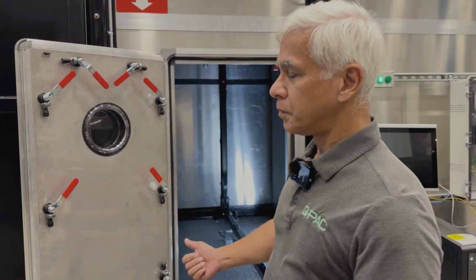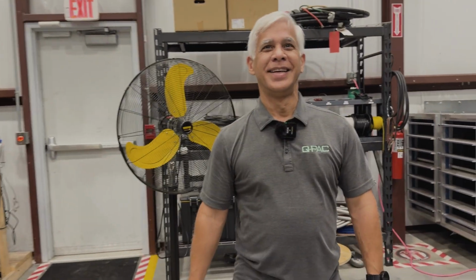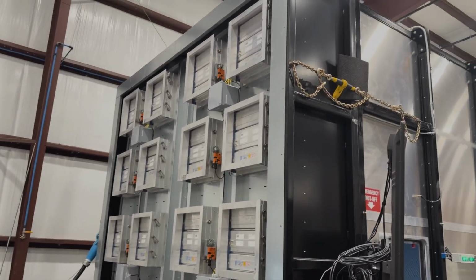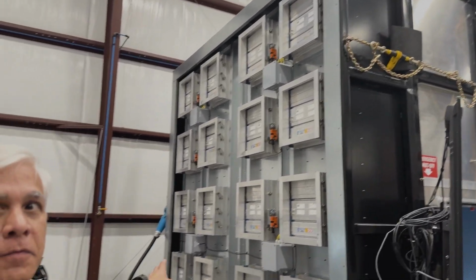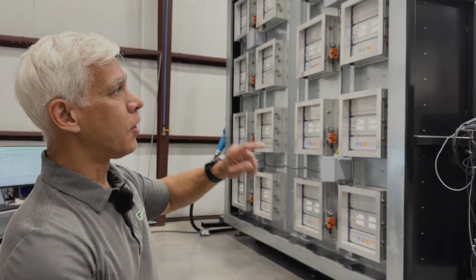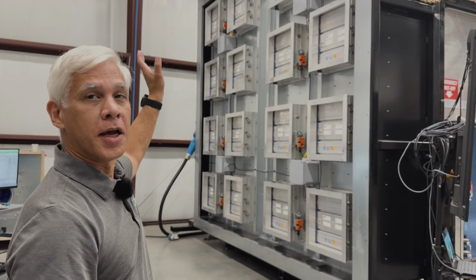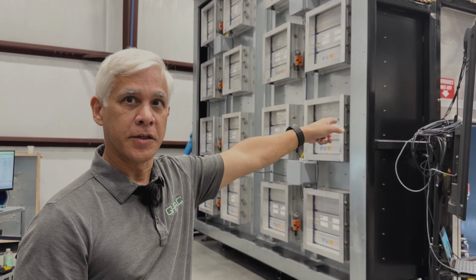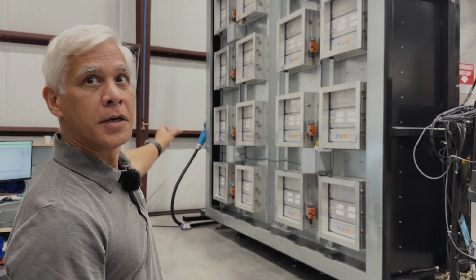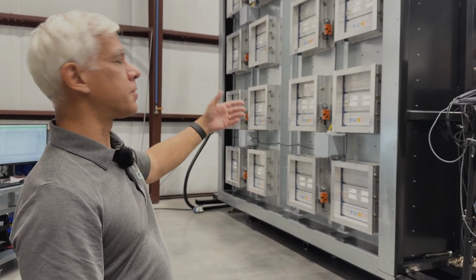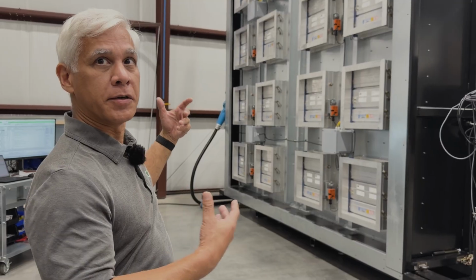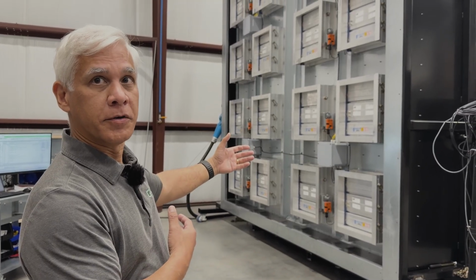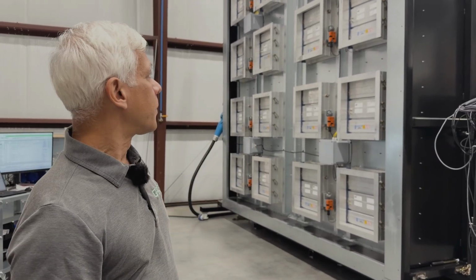That's going to bring some exciting tests down the line where we can swap a bunch of things out and try everything, and this guy over here is going to talk to us about that second. Yeah. And not only can we swap different supply fans here, if we need to, we can actually swap ends of the tunnel and move this fan to the front side, the exhaust side, and the test item to this side. So if there are reasons, for instance, if we're bringing in someone else's air handler that we want to test in a different configuration, we have that ability.